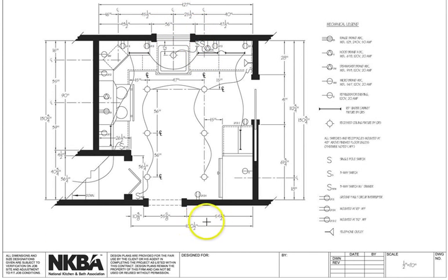On the mechanical plan, there are also some additional dimensions included, and those would be dimensions to any lights located in the ceiling. We have to let the electrical contractor know exactly where to place those light fixtures. Therefore, we provide center line dimensions to the center of each and every light fixture located within the ceiling.